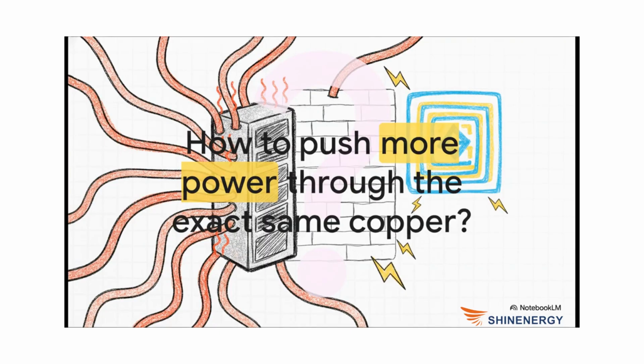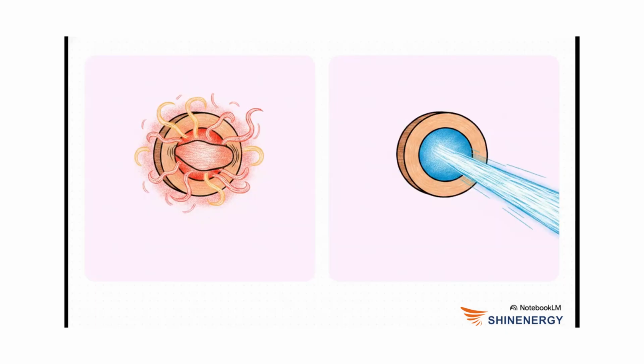Now, solving that introduces our next massive infrastructure hurdle. How do we push more power through the exact same copper wiring? Because even if we have the extra power unlocked, getting it from the data center floor into a rack that is demanding a full megawatt runs into a literal wall of basic physics. The physical copper wiring can only handle so much electrical current before it overheats and melts. So the crucial point here is that today's standard data center delivery is usually around 240 volts AC. When you try to push a full megawatt of power at that lower voltage, the required current is so astronomically high that it just overwhelms standard conductors, creating massive resistive losses.